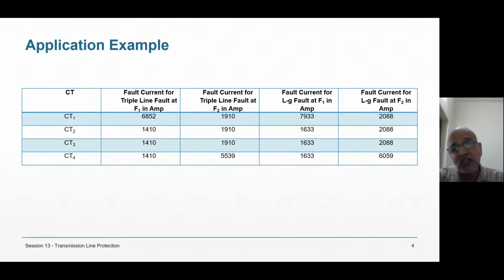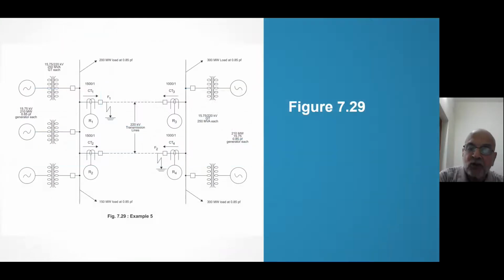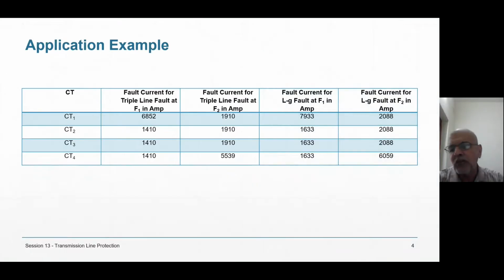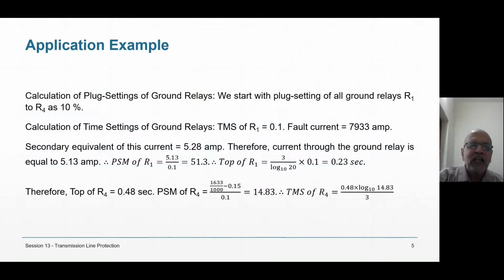Now you see, when a fault occurs at F1, maximum current flows through CT1. At other points, less current flows. And when a fault occurs at point number 4, F2, then CT4 has maximum current, and at other points less. So now if you go further, calculation of plug setting, R1 to R4. Now there is no final relay, no last relay. So we start with some relay.